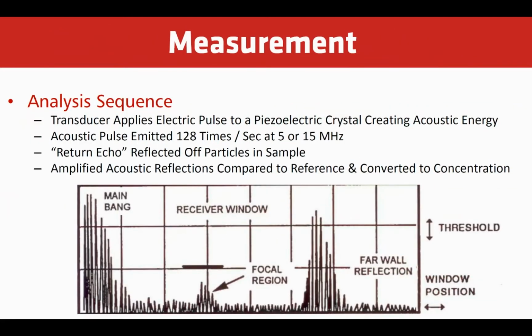Here's just a quick and easy look at how the analyzer actually works. The transducer applies a pulse to a piezoelectric crystal in the sensor head. And as you can see here, it generates what we call the main bang, or that is the sound generated, either a 5 or 15 megahertz. And what happens is if there's any particulates in it, or if we're talking oil and water, oil droplets in the focal region, it will respond and give an echoed pulse back. The proportion or size of this echo back is proportional to the ppm.